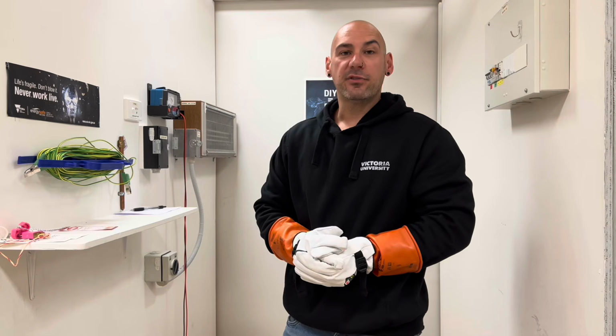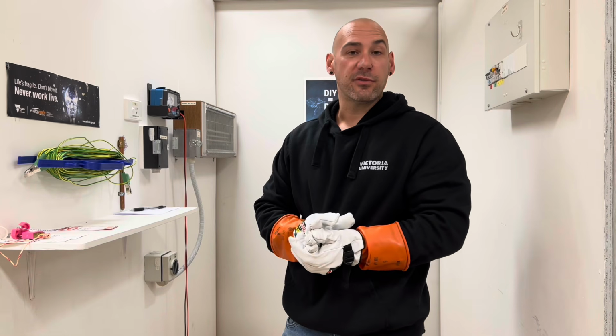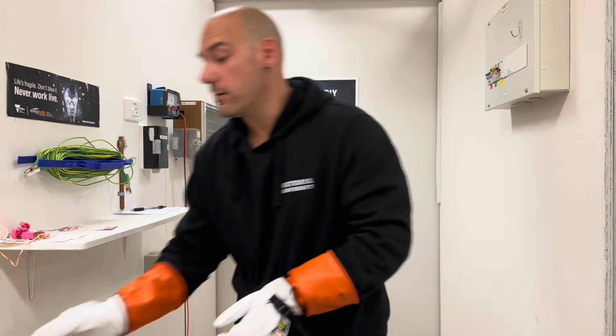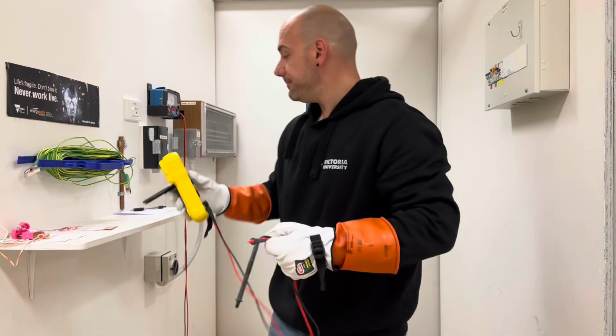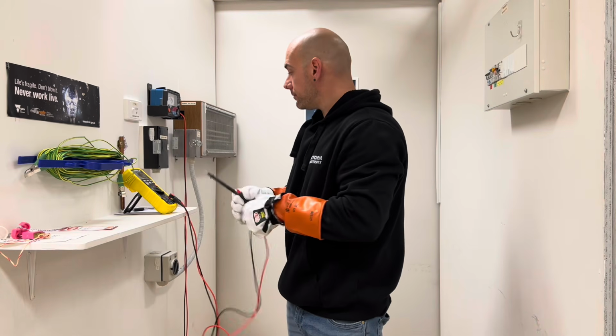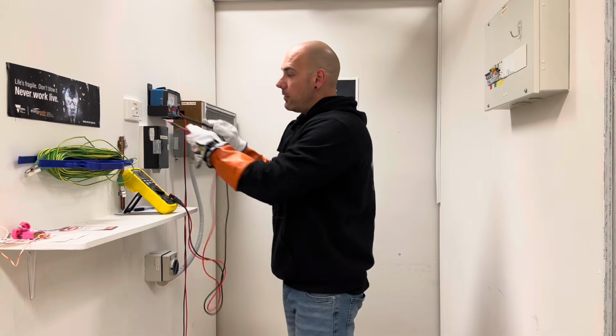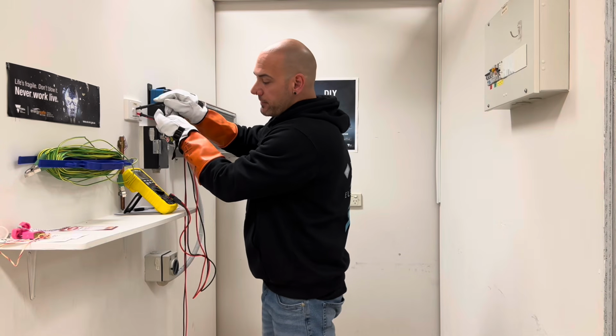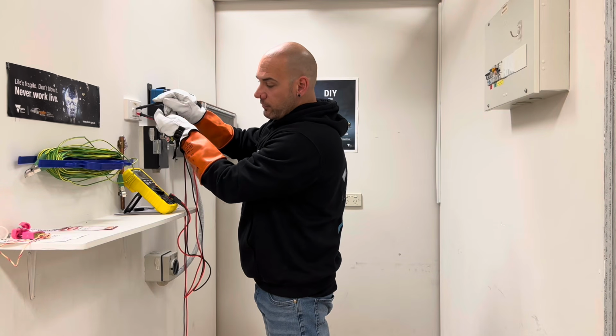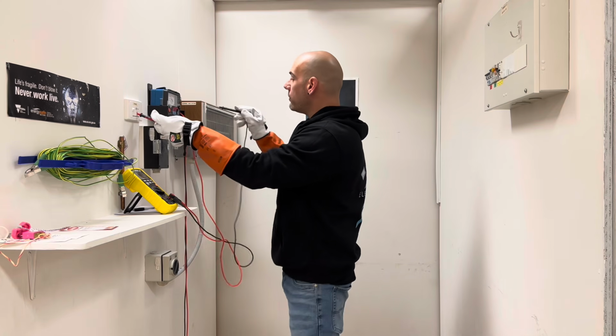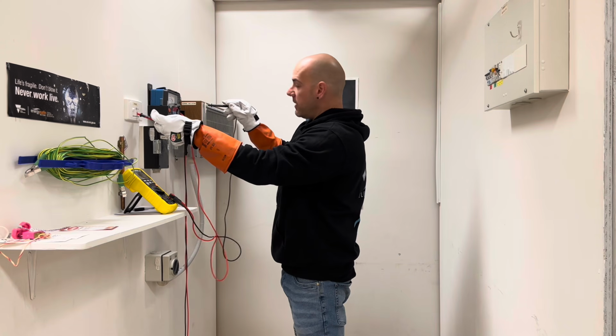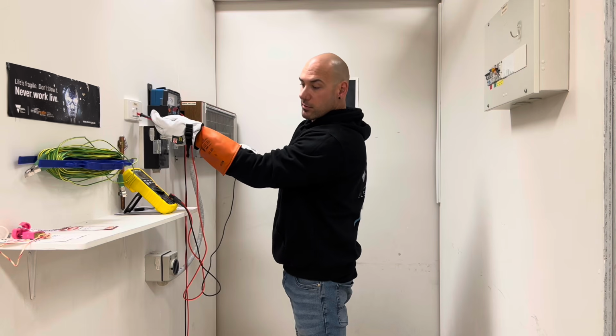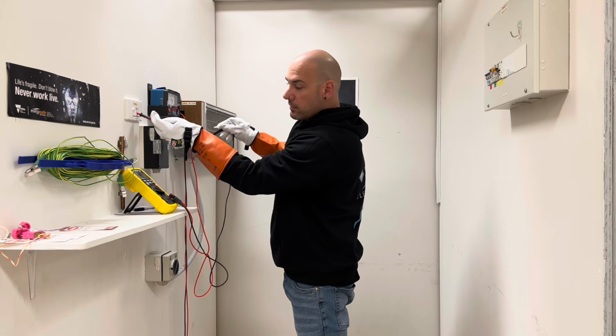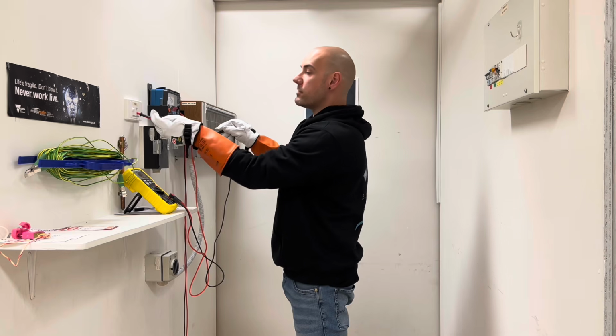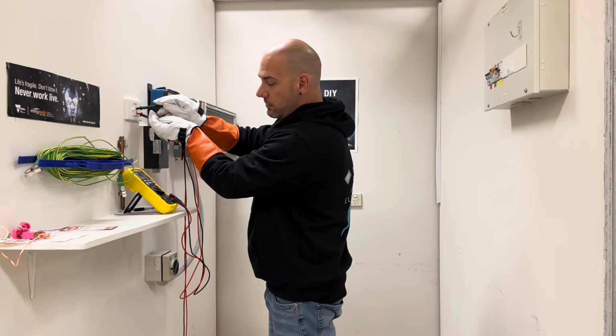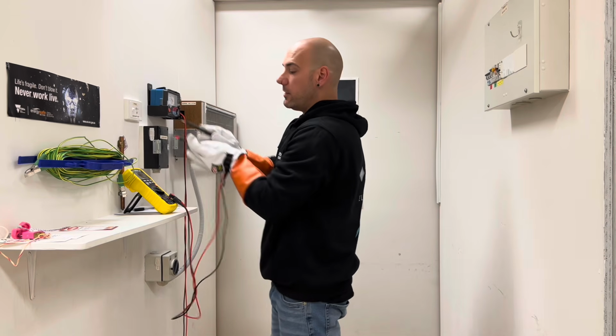At this stage, we're going to test the appliance frame to make sure there is no voltage on it. This is done by using a voltmeter. We will test our voltmeter on our reference voltage. We have 24 volts. We're going to test at least 3 spots on the heater's frame. Okay, the 0 volts present. Test our meter, and that is working correctly. Great.